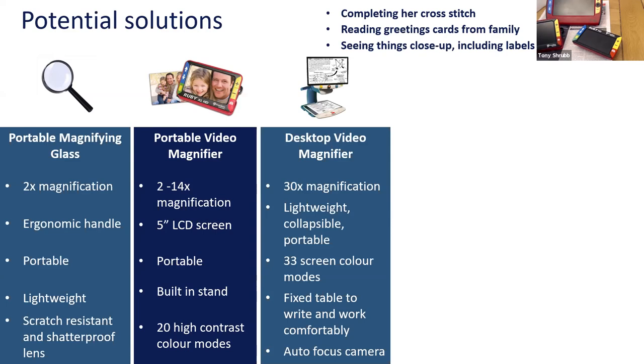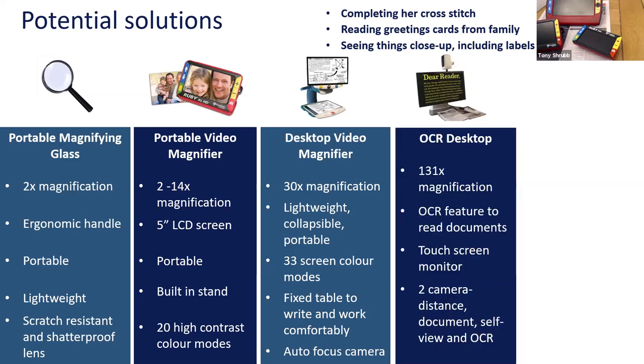The desktop video magnifier offers 30 times magnification. Some are lightweight, collapsible, and portable with a 12 or 15-inch screen; the one in the image is very much a desktop unit that stays on the table. It has 33 screen colour modes, an XY table, and an auto-focusing camera. The next desktop model features OCR — optical character recognition — which takes a snapshot of the page and reads it back to you, giving you audio output in addition to screen magnification.